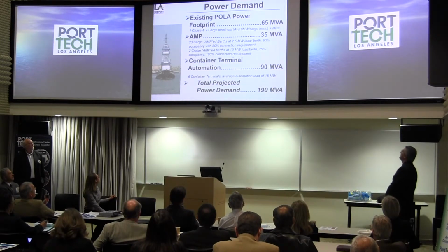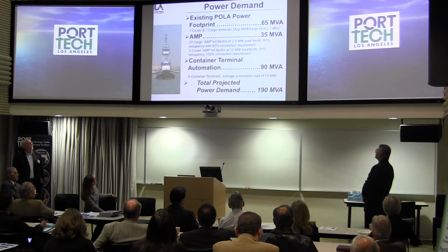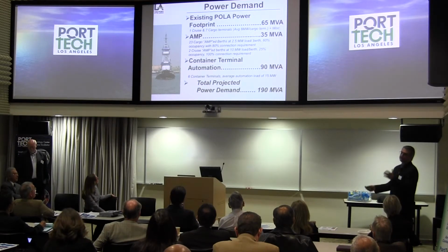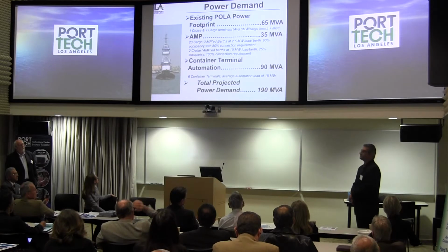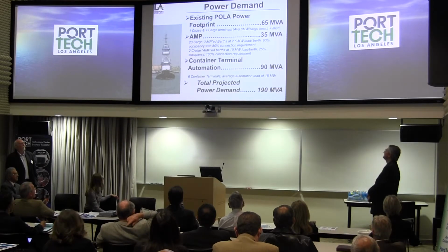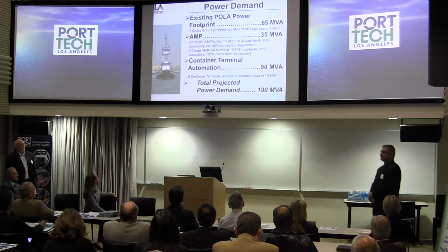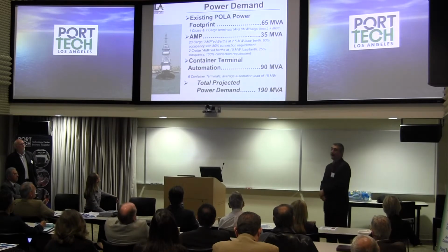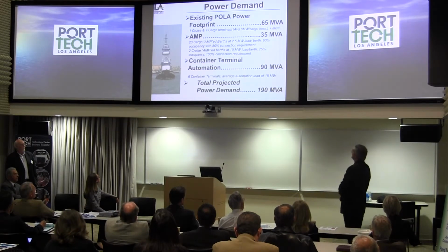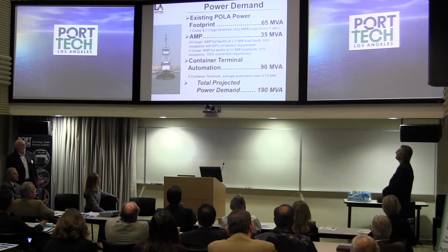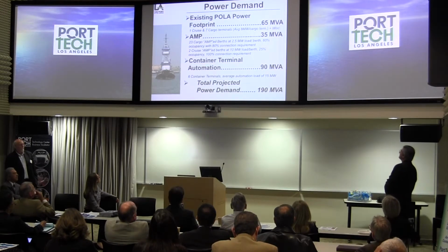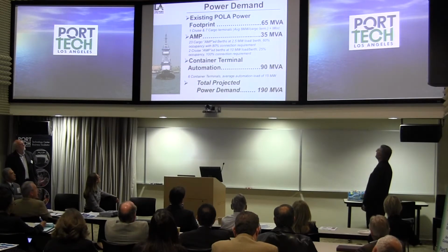For AMP, we have about 23 cargo AMP berths. Giving them the benefit of the doubt for maximum use, 2.5 megawatts each, 60% occupancy means 60% connected at any time, which is very high. With the 80% connection requirement per state, that translates to about 35 MVA.